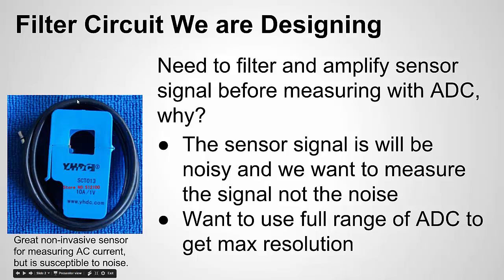The problem with these sensors is because it measures a field and has this wire that's not shielded, it picks up a lot of outside noise. You can almost think of this wire acting like an antenna and picking up high frequency noise. The reason we want to filter is we want to filter out the noise so we're measuring the signal. If we measure the noise we're not going to get a true or accurate reading.